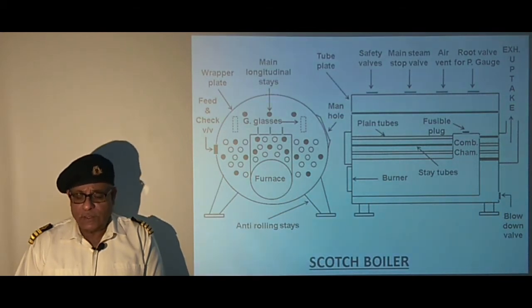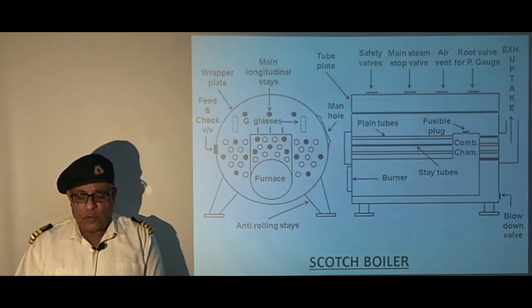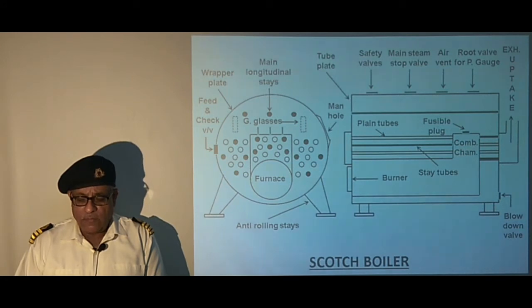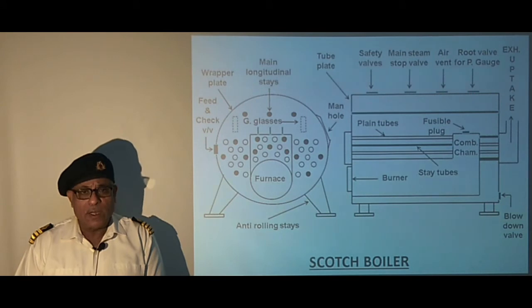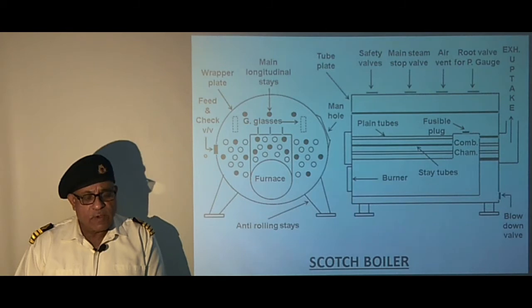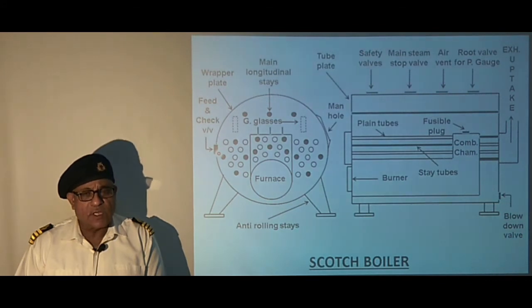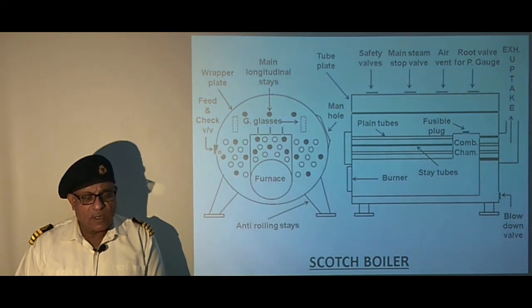The internal feed pipe is closed at the ends and is perforated throughout its length to distribute relatively cold feed water over a large space, avoiding local cooling of the hot boiler plate and tubes. Feed water is supplied through a feed and check valve, and inside there is an internal pipe with perforations so that cold water is distributed along the length of the boiler.